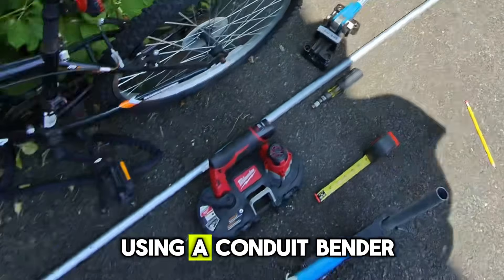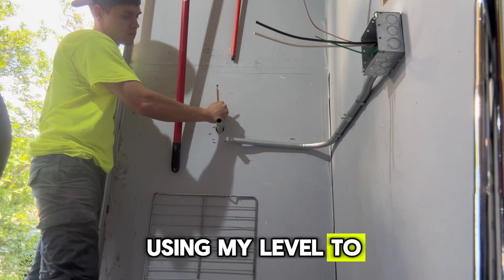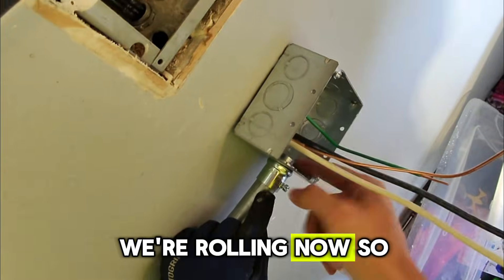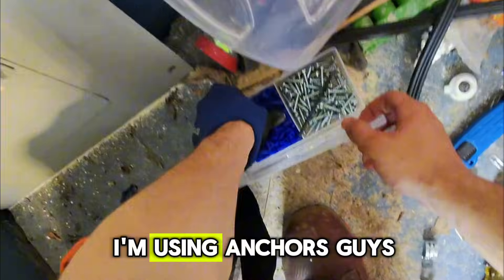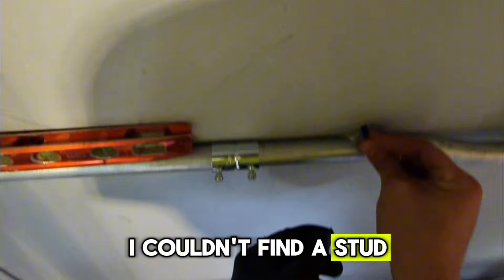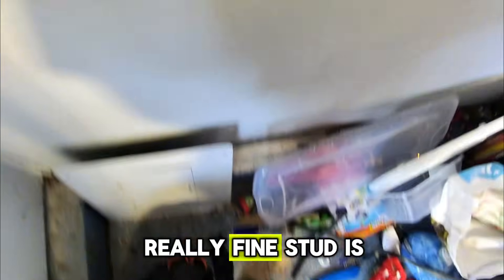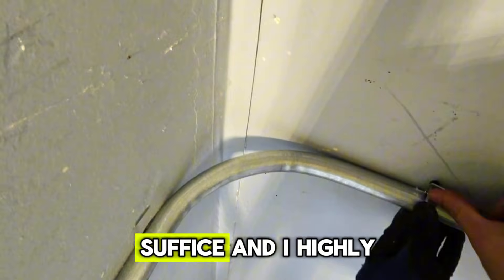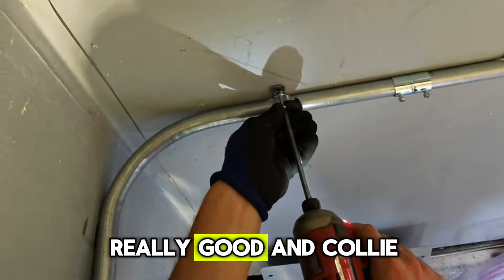I'm now using a conduit bender for my 90 degree on the wall, using my level to make sure it's straight. We're rolling now — got my EMT connector in and I'm now strapping in, using anchors the entire time. I couldn't find a stud so I'm going to use Molly anchors, which is completely fine. Studs are always better, but Molly anchors do suffice. I highly recommend getting the Molly set.